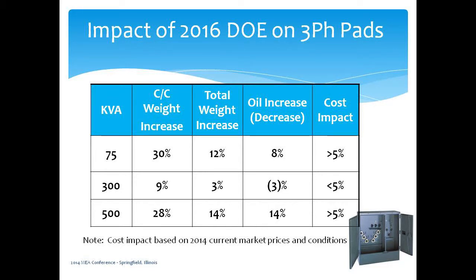Three-phase pads, you're going to see a significant increase in certain kVA sizes. There's just no doubt about it. All of those go through the top, you can't do a back load design, you always have to put them in through the top side. So you're going to see increases that'll, in some cases, I'll show a 28% increase in the weight of the core coil assembly on some of the larger kVA sizes.